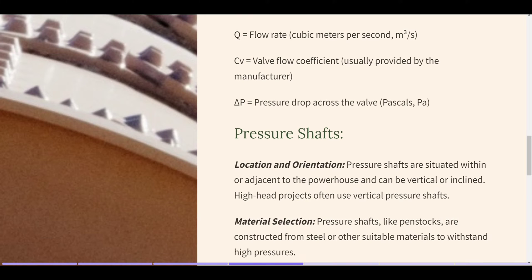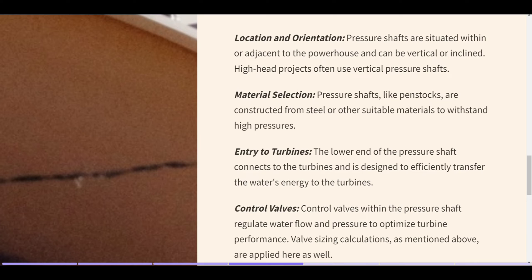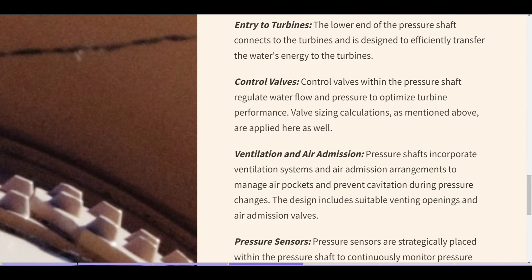Pressure shafts — location and orientation: pressure shafts are situated within or adjacent to the powerhouse and can be vertical or inclined. High-head projects often use vertical pressure shafts. Material selection: pressure shafts, like penstocks, are constructed from steel or other suitable materials to withstand high pressures. Entry to turbines: the lower end of the pressure shaft connects to the turbines and is designed to efficiently transfer the water's energy. Control valves within the pressure shaft regulate water flow and pressure to optimize turbine performance. Ventilation and air admission: pressure shafts incorporate ventilation systems and air admission arrangements to manage air pockets and prevent cavitation during pressure changes, including suitable venting openings and air admission valves.